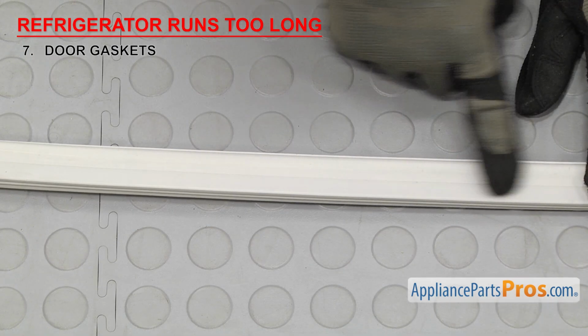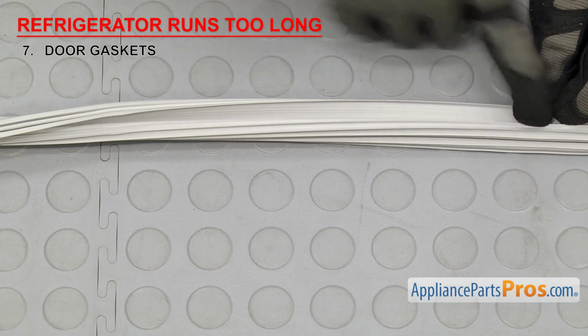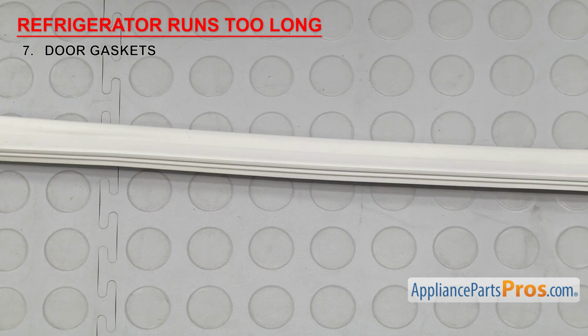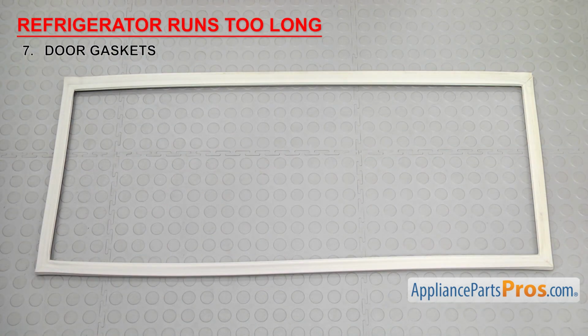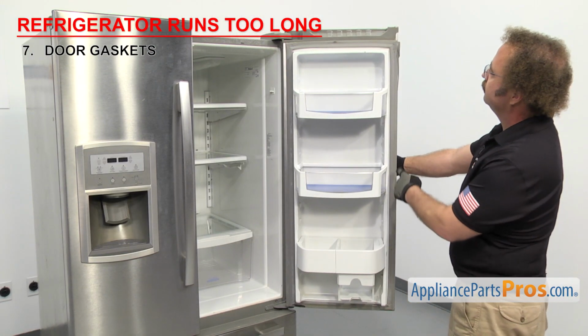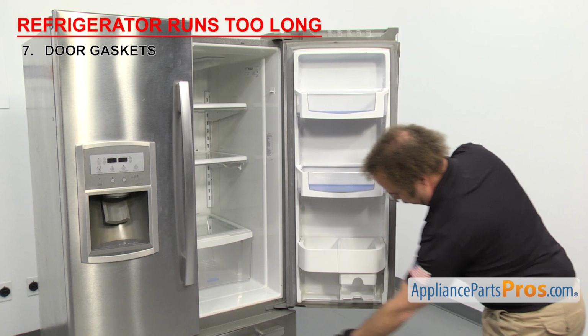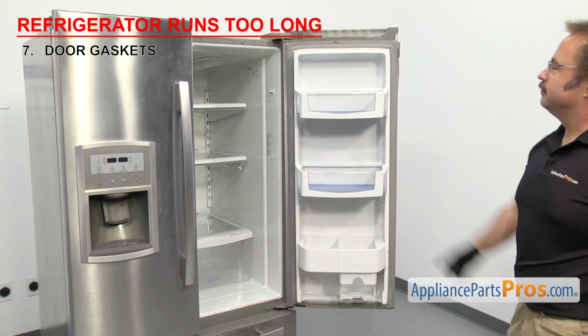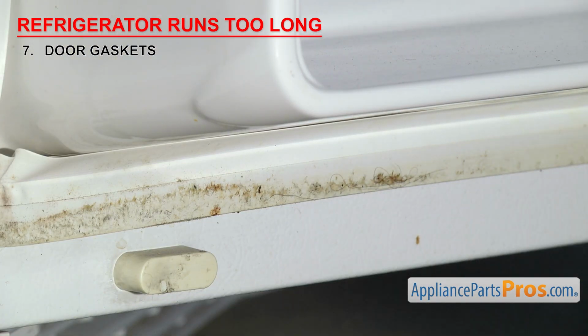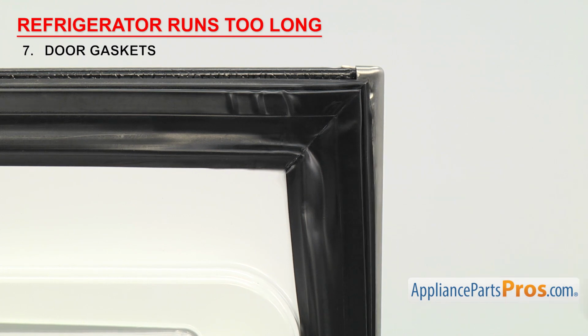Last thing to look at are the door gaskets. They seal the refrigerator doors. They usually have one flat side with a magnet, while the other side has a rib that mounts it to the door. They seal the door when closed to keep the warm air out and the cold air in. The gaskets are mounted on the outer edge of the door. If the refrigerator runs too long, it could be that the door gasket is either really dirty, especially along the bottom, or it's deformed, allowing warm air into that section, causing the compressor to have to run longer to bring the temperature down.